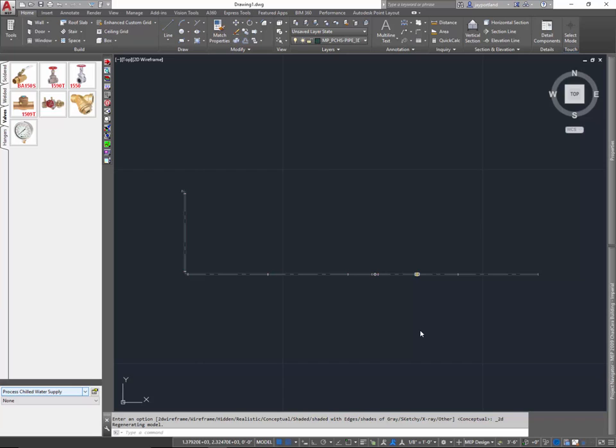The concept there is that we're not relying on design capability to get us from point A to point B and the routing of the piping between those two points. We're actually going down to the precision of what's actually manufactured and how you actually spool the piping so that it works perfectly the first time without having to recut, at a fabrication level of intent. So Fabrication CADmep on top of AutoCAD MEP. Let's take a look at how we use this.